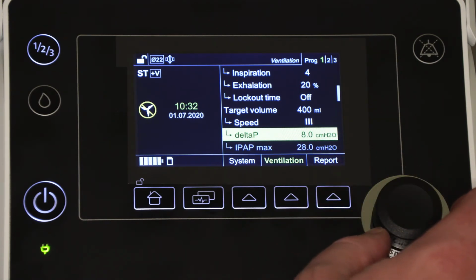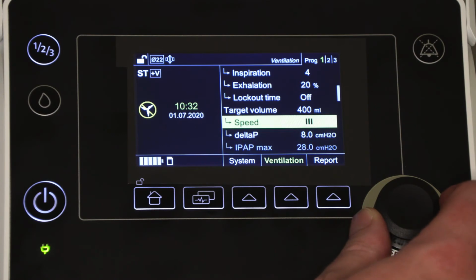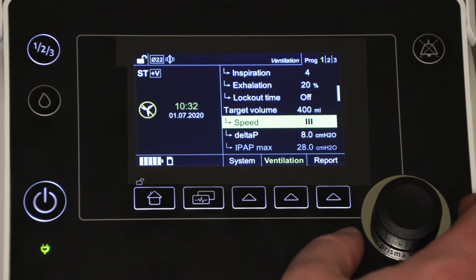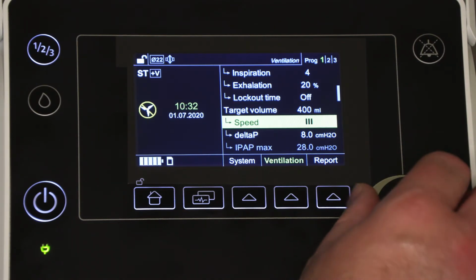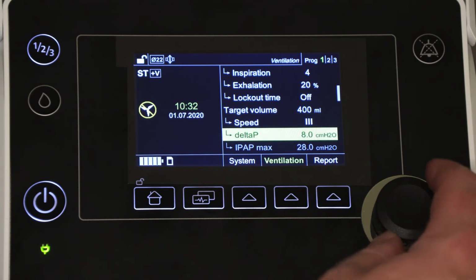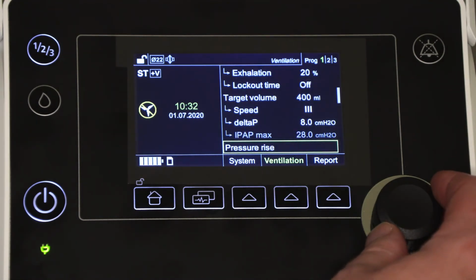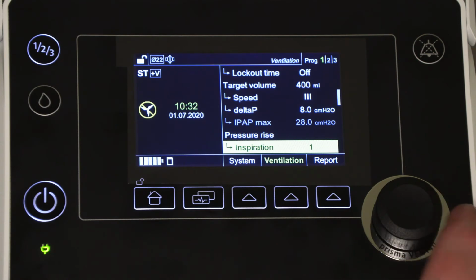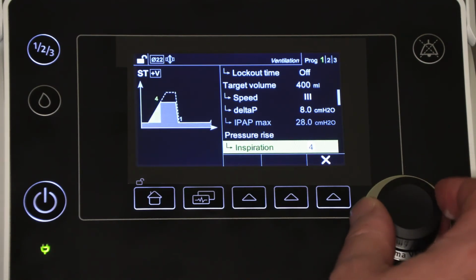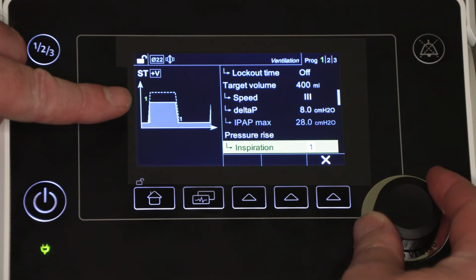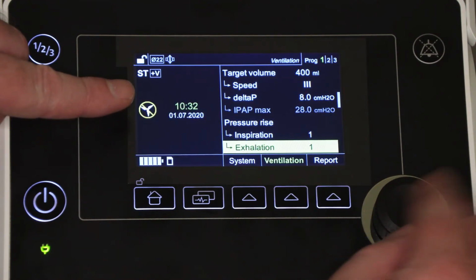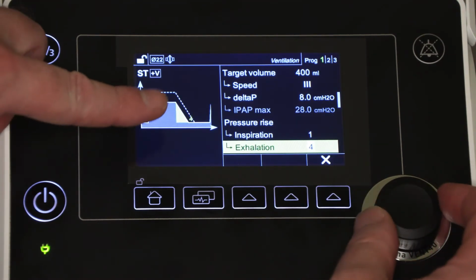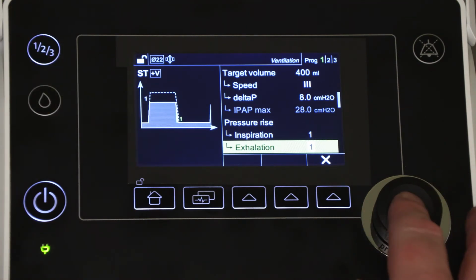The stages at which the pressure will increase during this process depends on the set reaction speed. If the max IPAP is reached, but the target volume hasn't been achieved, the IPAP will not increase further. The target volume can just be left turned off if it's not required. The pressure rise controls how quickly the pressure goes from EPAP to IPAP for inspiration or from IPAP to EPAP for exhalation. There are 4 adjustment stages for each setting, and the diagram on the left of the screen will demonstrate the slope achieved.